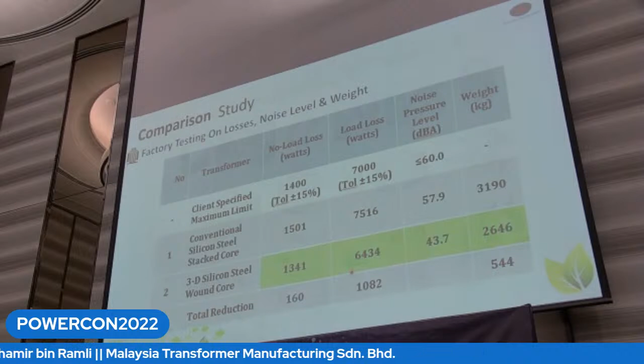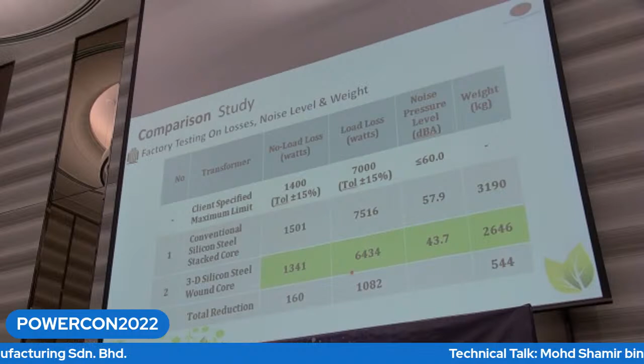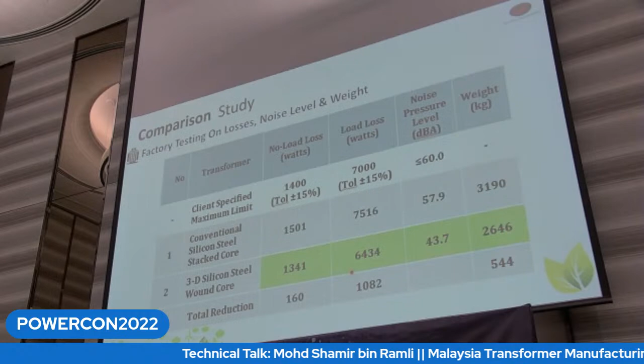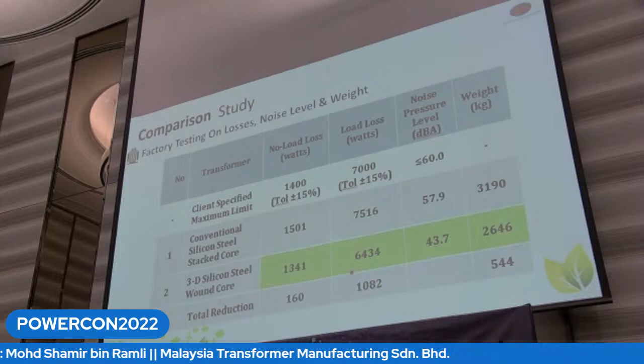So in terms of the comparison study, for a conventional silicon steel stack core, the no-load loss is about 1,500, and the load loss is 7,516. The noise pressure is about 57.9, and the weight is 3,190 kilograms. But with a 3D silicon steel wound core, the no-load loss is lower at 1,341. The load loss is 6,434.